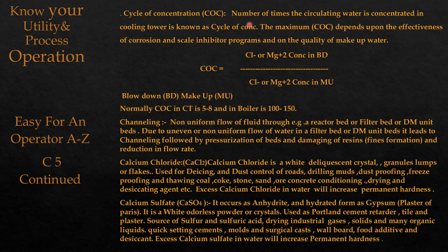If you want to know more about this cycle of concentration, you can watch my previous videos. Normally, COC in cooling tower is maintained as 5 to 8 and in boiler as 100 to 150. Now we can see another important terminology in refineries and in water treatment: channeling.